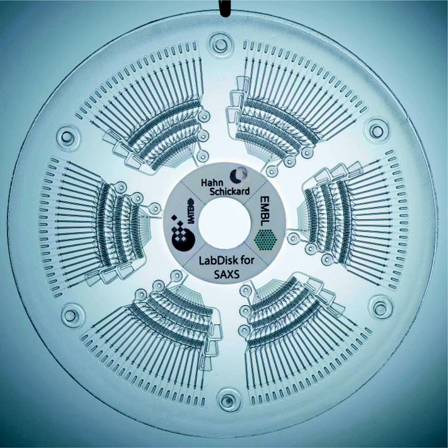There are a few commodity plastics that have emerged as suitable for medical microfluidic applications. These include poly methyl methacrylate, PMMA, polystyrene, polycarbonate, and a variety of cyclic polyolefin materials. PMMA has good optical properties for fluorescence and UV detection modes, and is relatively easy to seal to itself. These are available in grades suitable for both injection and compression molding.